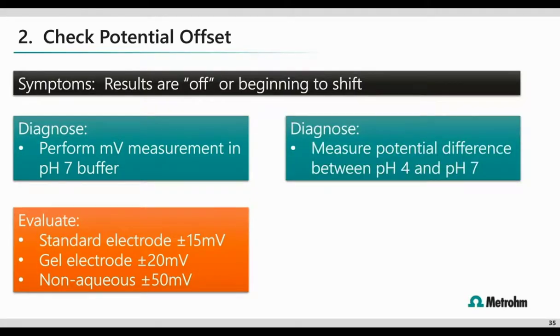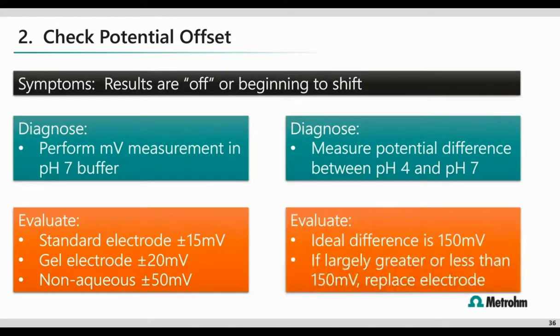You may also measure the potential difference between pH 7 buffer and the pH 4 buffer. Just repeat the previous procedure to determine the millivolt measurement for pH 4. Determine the difference between pH 7 millivolt reading and the pH 4 millivolt reading. Consider replacing the electrode if the difference is considerably higher or lower than 150 millivolts.